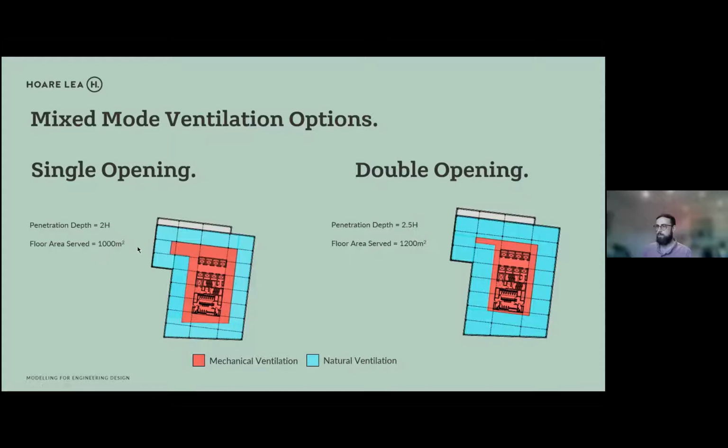service from natural ventilation. So these are the blue areas where we could do some mixed mode. The red zones, it's determined, probably won't get enough natural ventilation through to do fully mixed mode. So the control within the red zone is just normal operation based on mechanical ventilation.